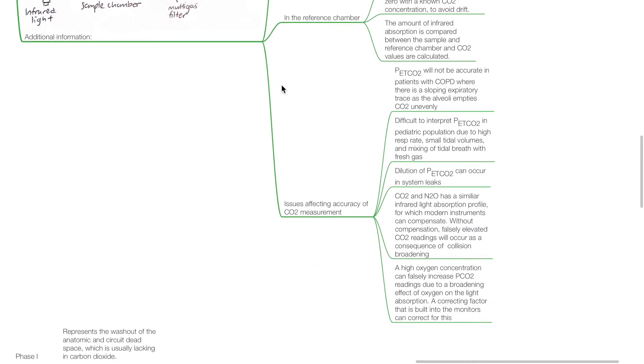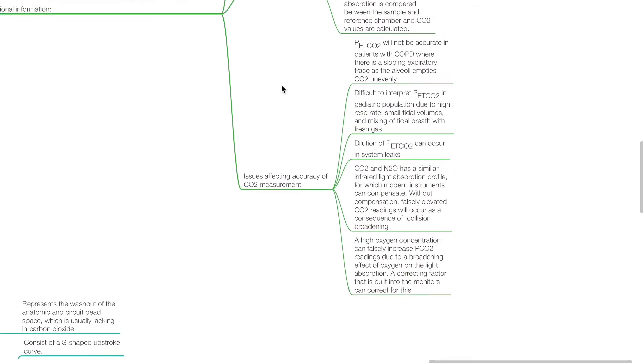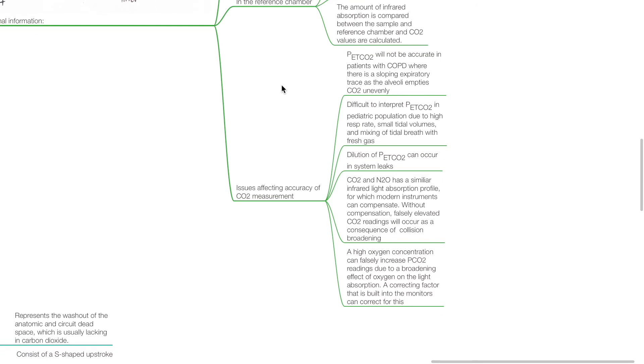Issues affecting the accuracy of CO2 measurement include: ETCO2 will not be accurate in patients with COPD where there is a sloping expiratory trace as alveoli empty CO2 unevenly. It is difficult to interpret ETCO2 in the pediatric population due to high respiratory rate, small tidal volumes, and mixing of tidal breath with fresh gas. Dilution of ETCO2 can occur in system leaks.